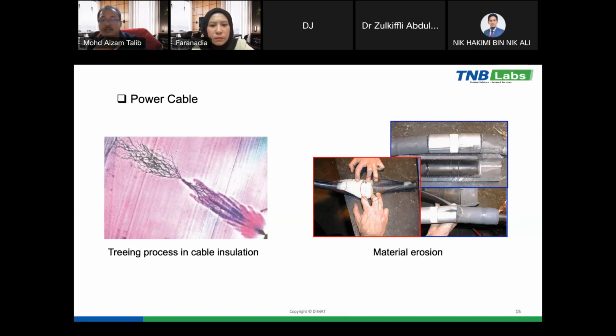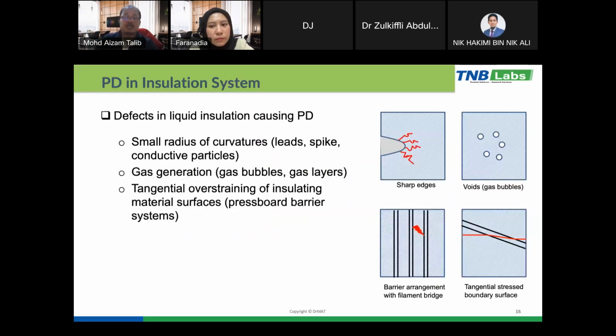This is an example of joint failure. When we cut the cable and open the cable joint, we can see the erosion of the joint material. So these are examples of the presence of partial discharge in rotating machines, transformers, cables, and also overhead lines. So, partial discharge in insulation systems.